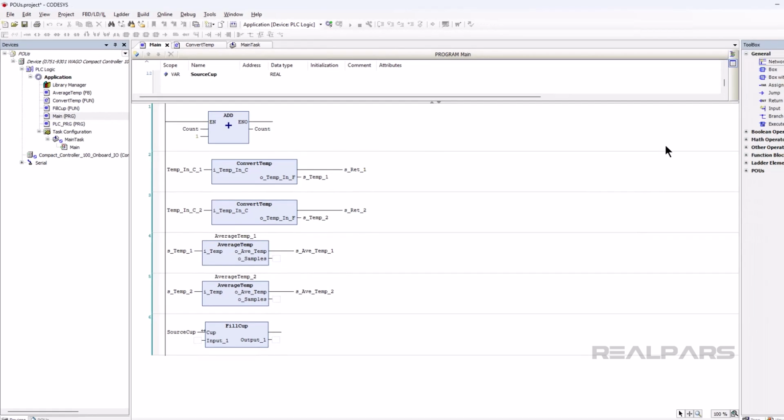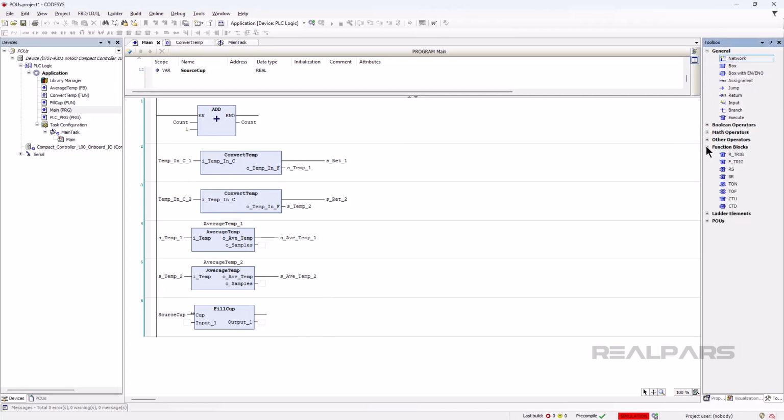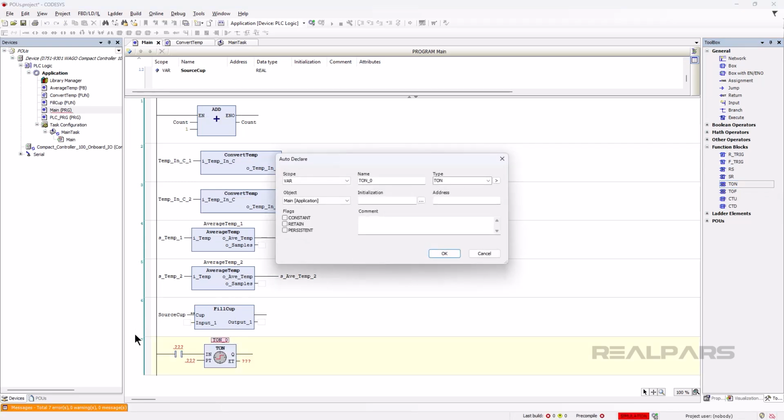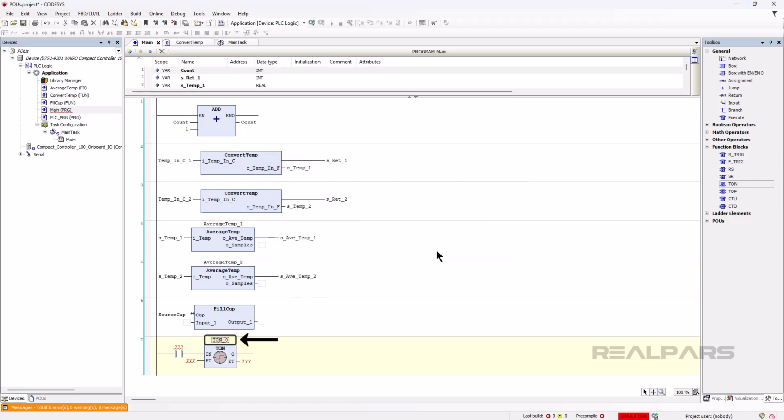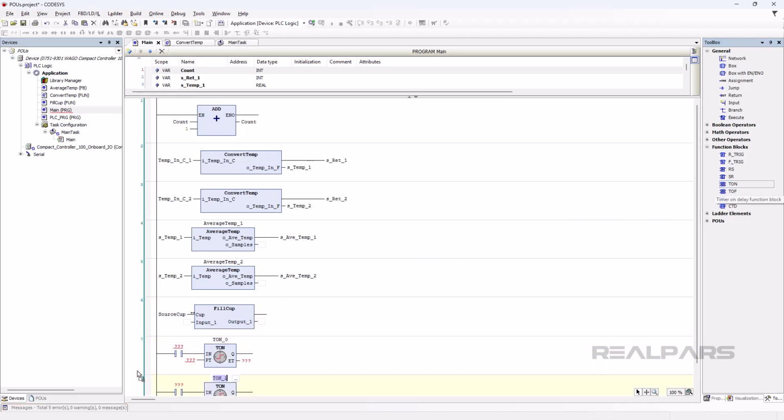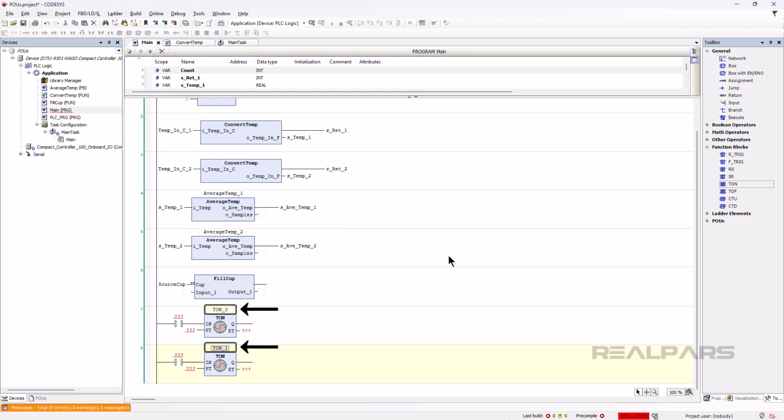This can be a bit confusing to think about, so let's look at a concrete example. A timer is a function block POU that you have probably worked with before. Each time you create an instance of a timer in a CODESYS project by calling the function block, you have to define a variable that stores the data for that instance. A project can have multiple instances that all behave independently of each other because each instance has its own data.